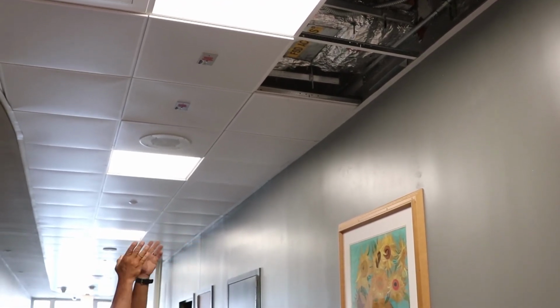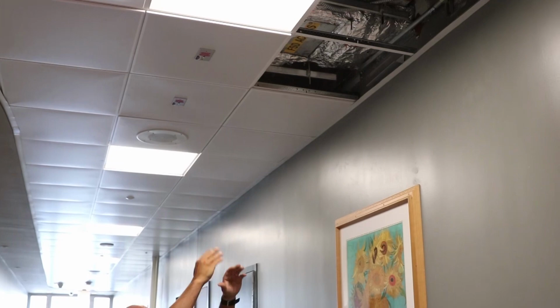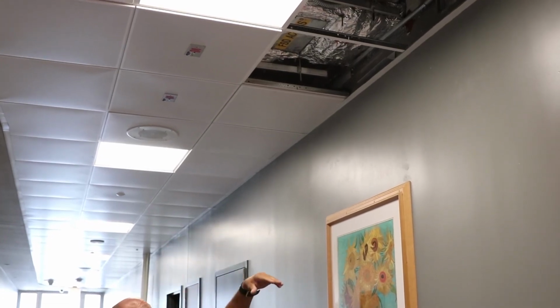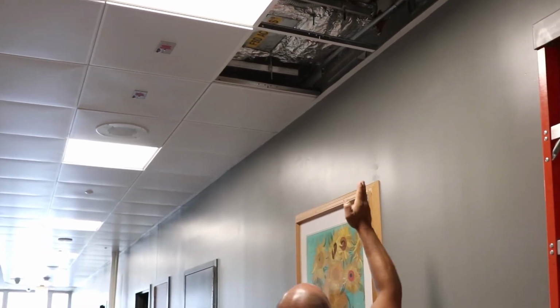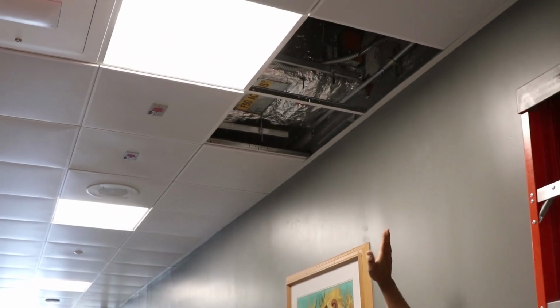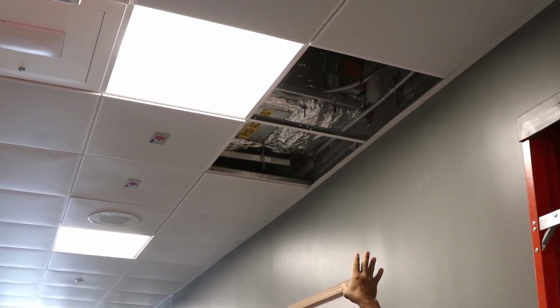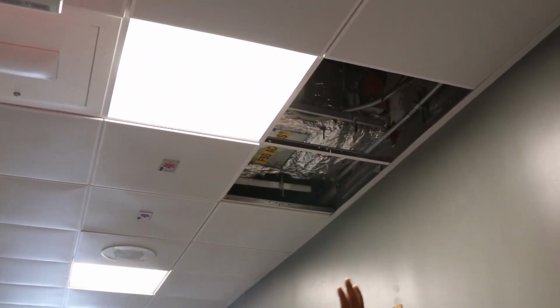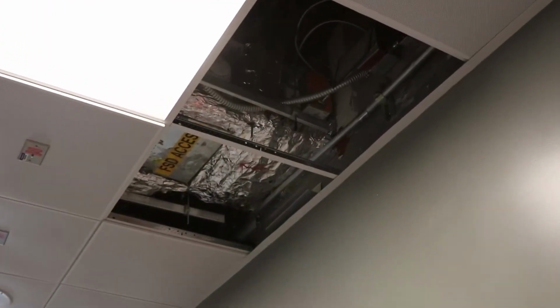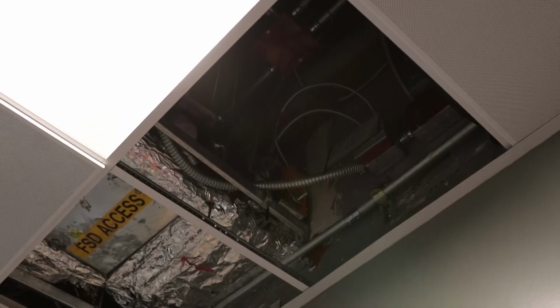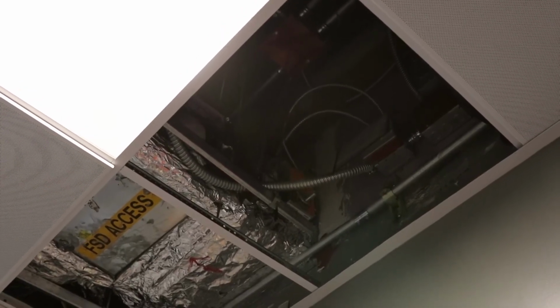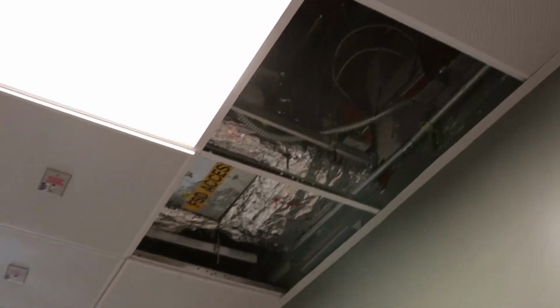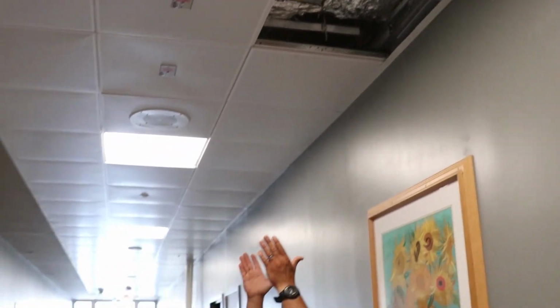Okay, so there's a smoke detector in each duct, and you'll see a relay package next to each damper. So here are the dampers against the wall. This is another Belimo style fire smoke damper, smoke detector, relay package. If I was to pop this tile, it'd be the same. And as we rode this up, if you were to walk out that door and walk up in the same location, this is gonna be the same configuration. It's gonna look exactly the same.